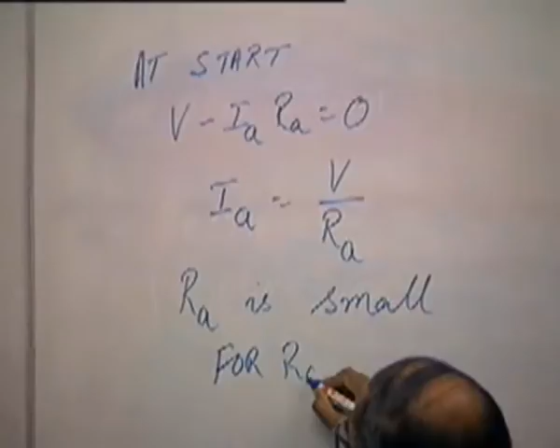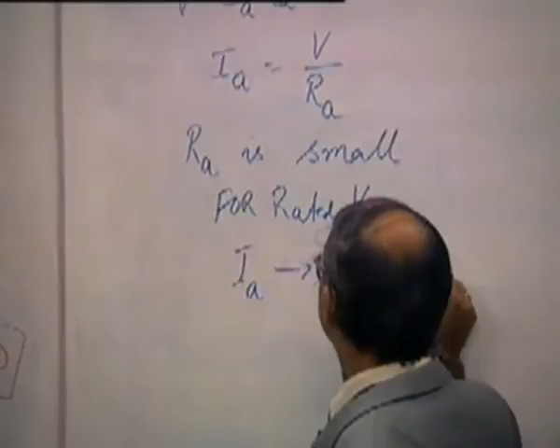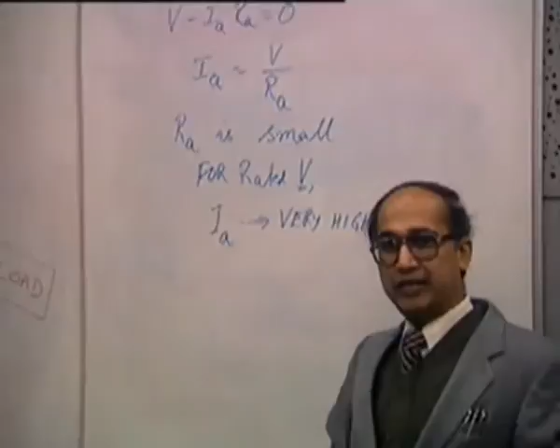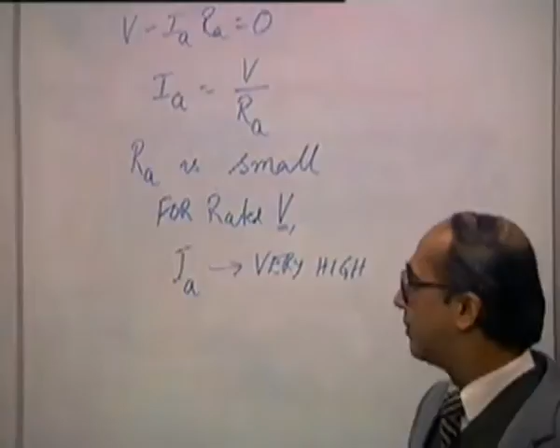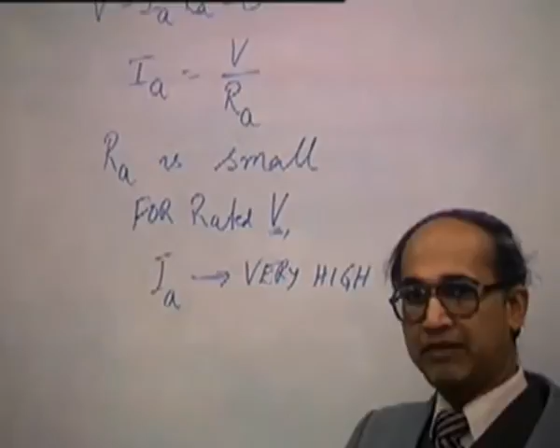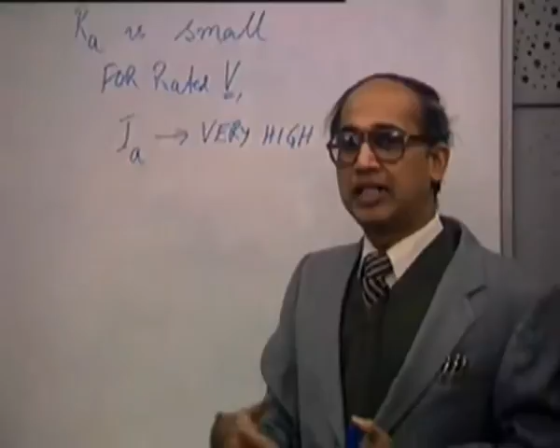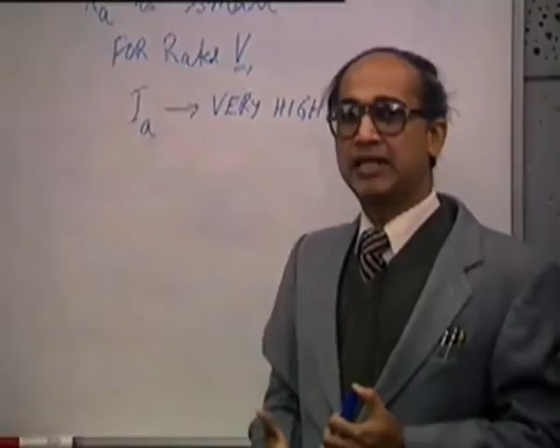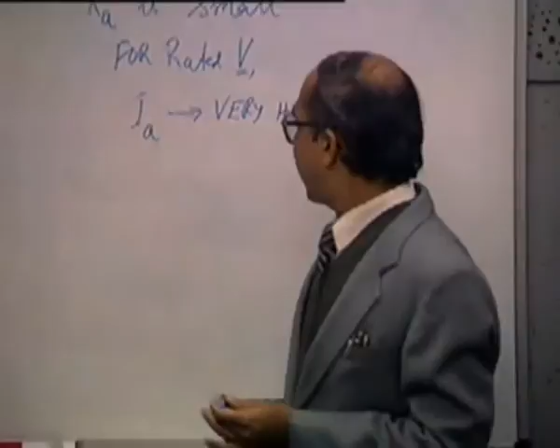Therefore, for rated voltage, IA is very high. So if you apply rated voltage, the current will be very high. Now, if at starting a very high current is flowing, and if the starting period continues for sufficiently large time, which generally happens with loads with high inertia, we will have sustained high currents in the armature windings, and with sustained high currents, it will add up to increased losses and heating, which may ultimately result in the burning of the windings due to failure of insulation. Therefore, high IA is undesirable.